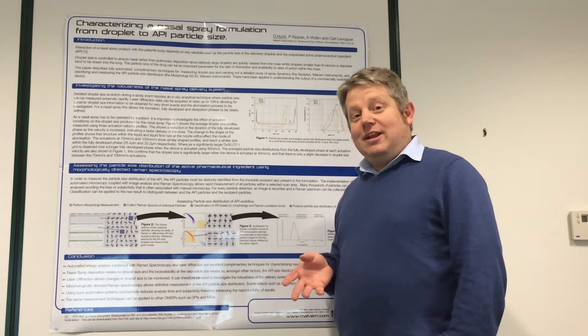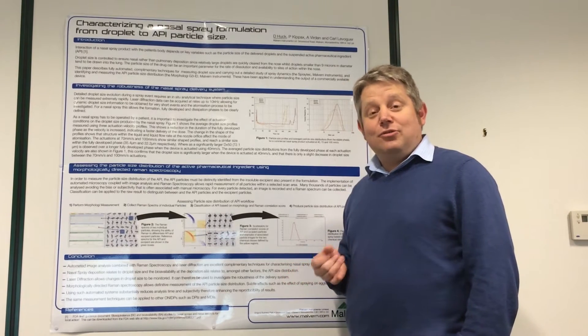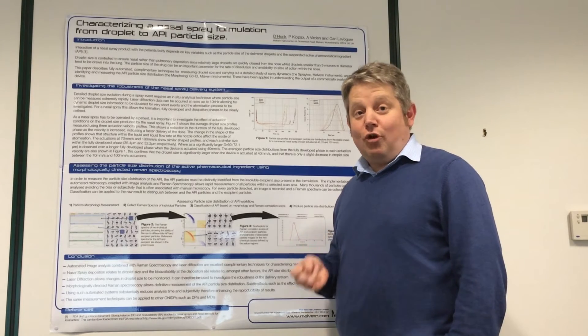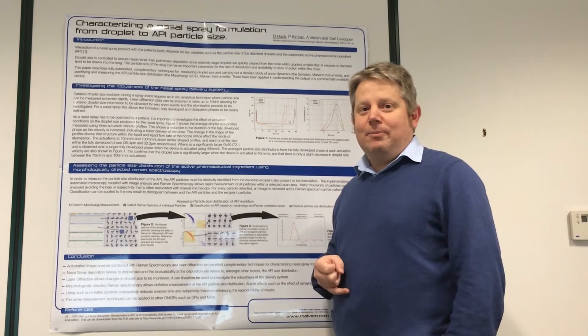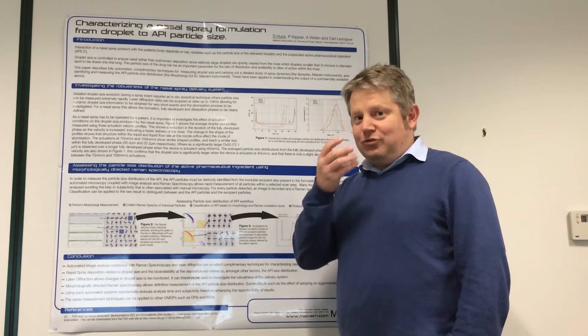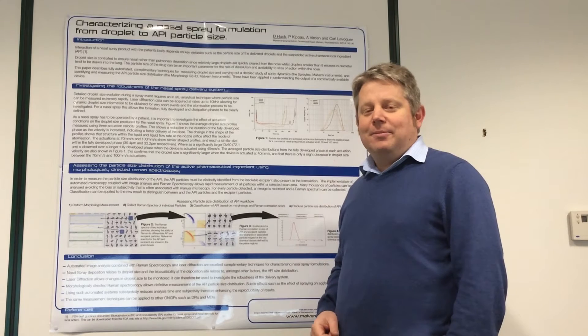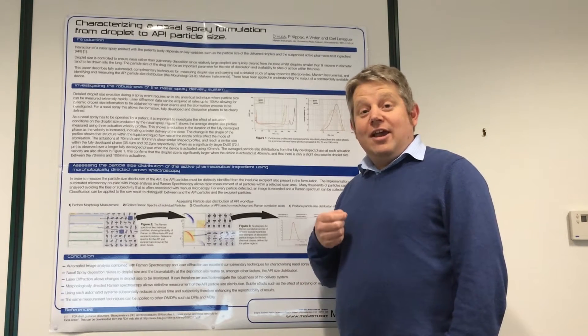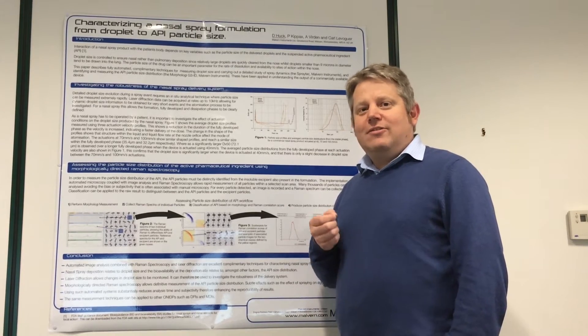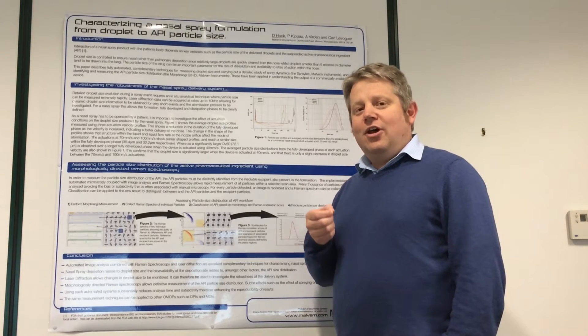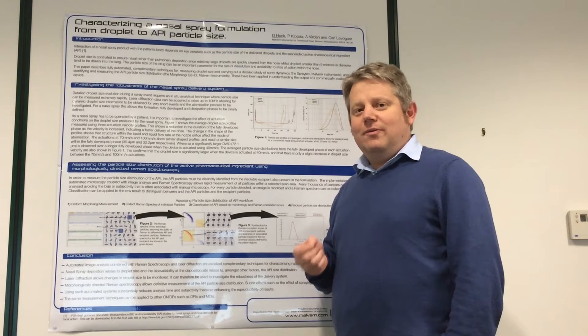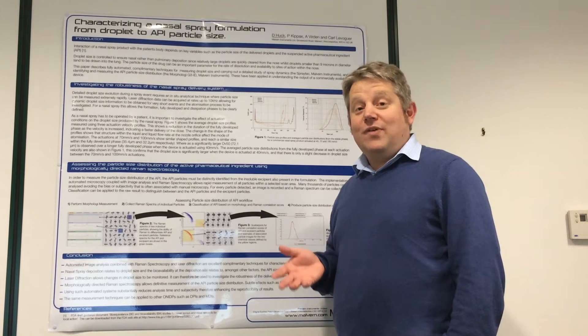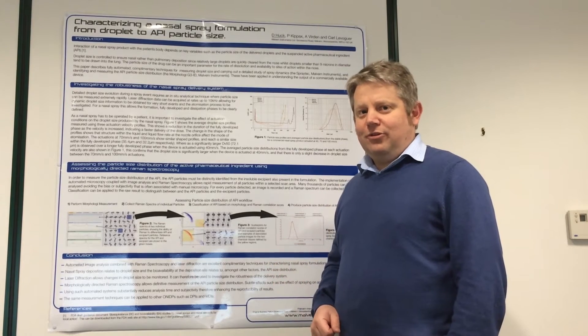When a drug is delivered by a nasal pump spray, there are two things that we need to consider. First, what are the size of the droplets produced by the pump? Because that tells us about where those droplets will end up in the nasal passages. And secondly, if it's a suspension formulation, we need to know about the particle size of the drug within those droplets, because that can relate to the bioavailability of that drug substance.